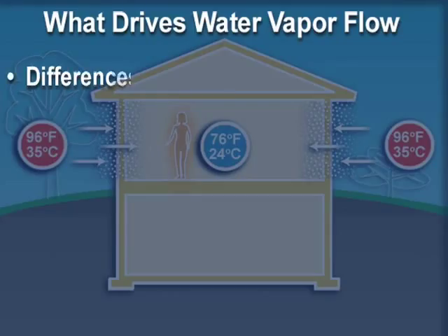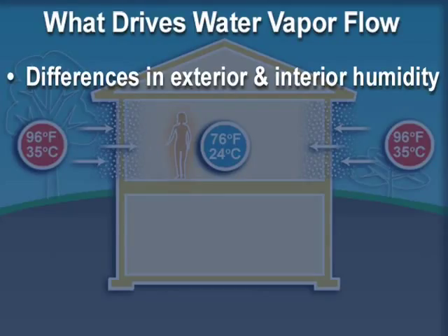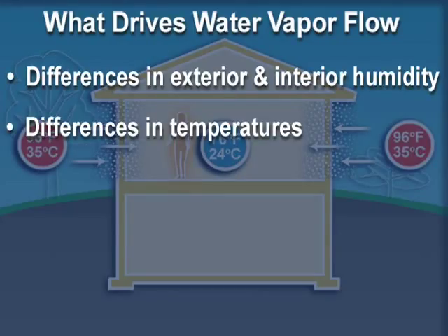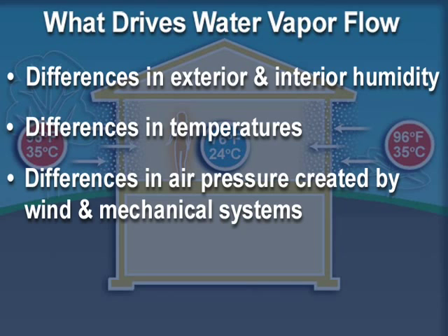We've discussed the importance of preventing liquid water from entering our building from the outside. Let's not underestimate the importance of managing water vapor flow, both from the outside in and the inside out. The amount and direction of flow will be driven by differences in exterior and interior humidity, differences in temperature, and differences in air pressure created by wind and mechanical systems, such as forced air furnaces and large exhaust fans.